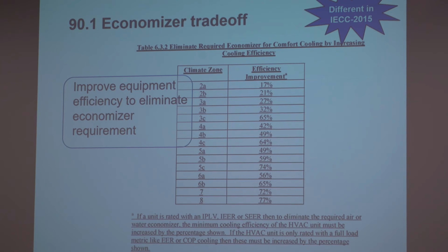We wanted to give people options instead of just not doing it at all, an air economizer or a water economizer. You can instead use one of these. And it doesn't work in the really cold climates. Like I can't imagine ever finding something 59%, 64% more efficient. It's really difficult. But in climate 4, I think you're pretty close. 49% in 5A, you might get pretty close depending on the class of equipment that you're looking at. Again, this is not just for unitary. This works for chillers. This works for other pieces of equipment that are more applied than we used to have as well. Any questions on this?